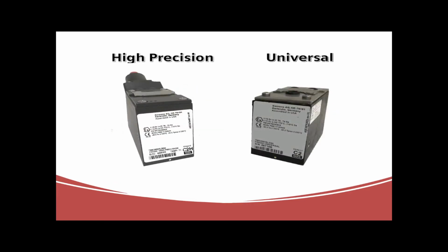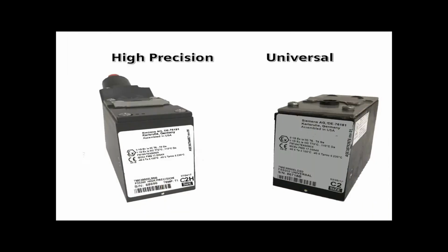Their labels identify their type, whether the sensor is a universal or a high precision. It also identifies their size. You'll need this info for your flow meter programming. The part number also identifies the sensor type and size. HP and universal sensors are completely different, so you'll want to be sure you've properly identified the type you are using along with the size.